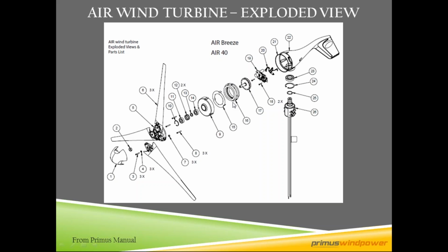The stator produces what we call wild AC, unregulated AC, which then goes into the circuit card where a rectifier block converts it to 12, 24, or 48 volt DC. The turbine is voltage specific, so you have to match the turbine's voltage to your battery bank's voltage - it's not field adjustable for that. There is field adjustability within the potentiometer, which I'll talk about in a minute, but you do have to buy the turbine voltage specific.